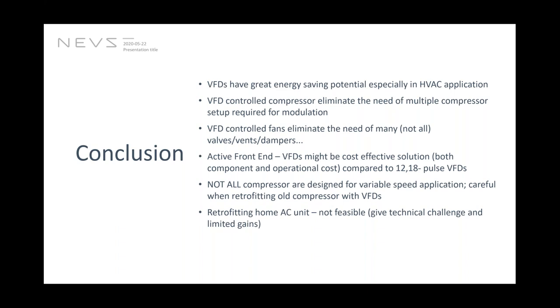This is not based on any hard numbers. It's based on the application and benefits that I saw when comparing these two, active front end and multiple pulse front end VFDs. But there might be some other hidden costs that I have not accounted for. And finally, for the retrofitting, it's important to mention that not all compressors are designed for variable speed applications. So we must be very careful with the retrofitting of old compressors. Very, very careful. It might be unsafe in the end.